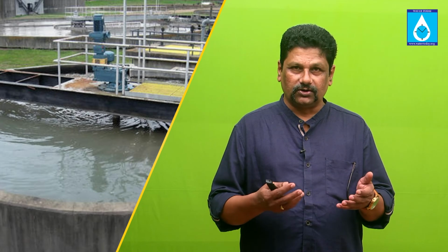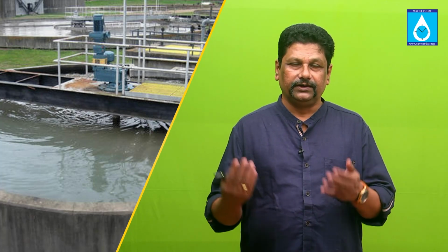So you need to have some calculations done, and as a rule, what they say is, if the geodetic head is less than 40% of your total head, then your VFD will work. If it is equal to or greater than that, your VFD is not going to work. So when you think about VFD in a sewage pumping operation, you can think about it when you're doing a soft starting or something, but you need to be very careful about using the VFD on a sewage pump. So get in touch with the experts and they'll be able to give you more information on it.